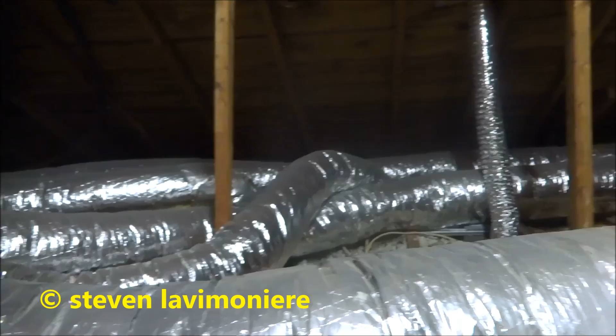So 3.5 tons is just definitely not what we need here. I'd like to put another return in if I could. Well, that's 12-inch going down there. We got a 12 dumping down in the hallway. That's a whole ton right there. So 4 8s, a 6, a 12, and obviously this return's not enough. That's it.